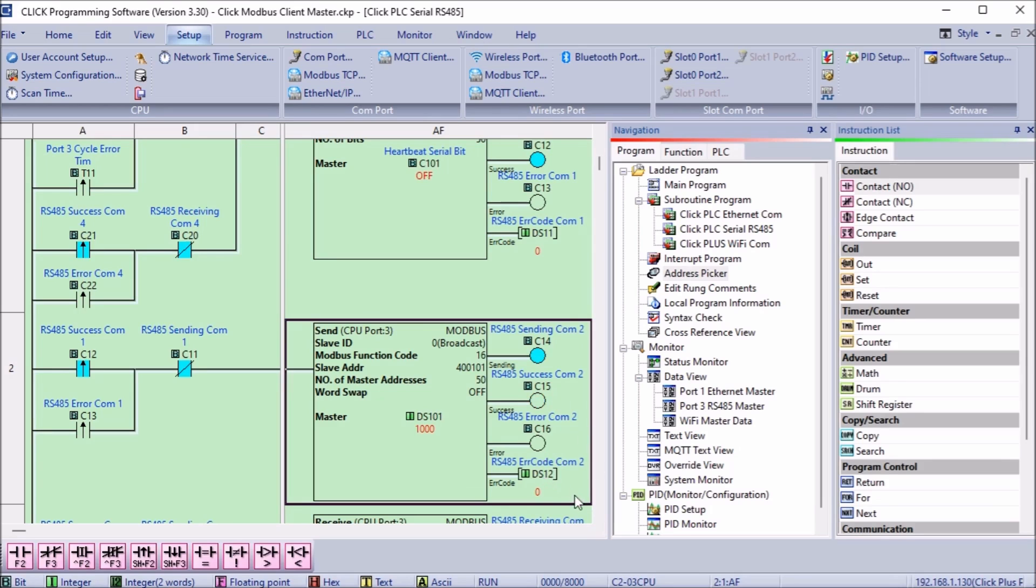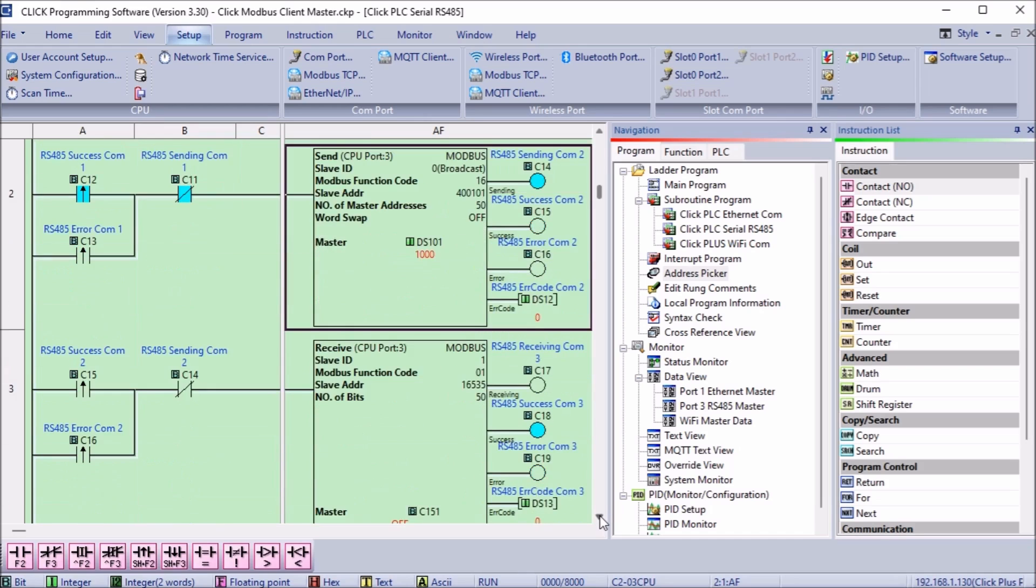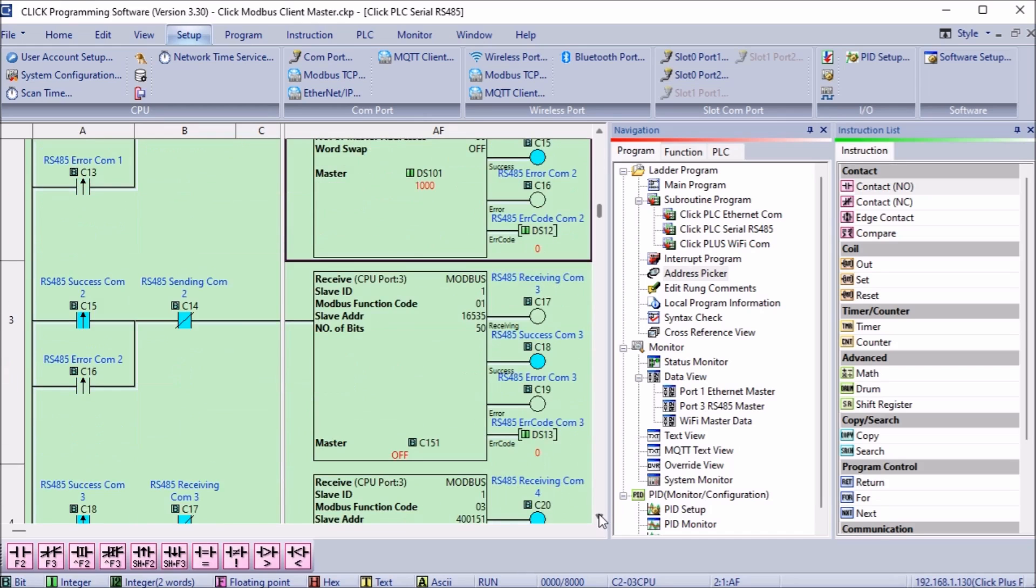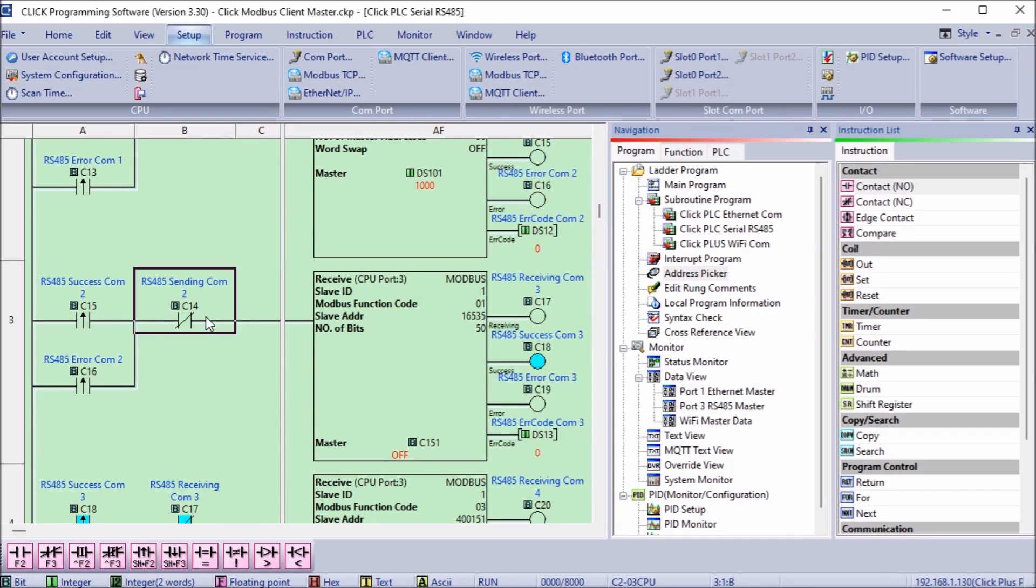The flags from the second send instruction will now trigger the receive instruction. The receive instruction function code will read coil status. This will read 50 bits starting at 16535 which is address C151 of the slave PLC and write them to the master starting at C151.